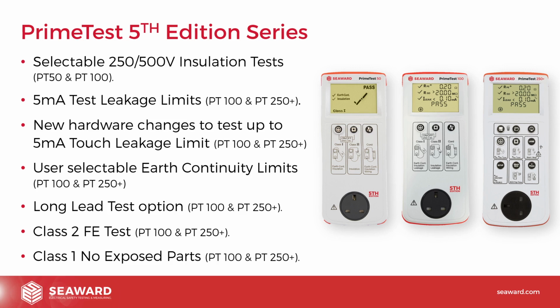So less skilled users, and we talked earlier in the webinar about the level 1 users, level 1 competency, will be able to carry out tests knowing that they're not going to damage any equipment and they're not going to have to change the settings or anything like that. So it defaults to 250 volts. And if you want to test at 500 volts, you hold the test button down longer and it changes over for that particular test to 500 volts. It'll carry out the 500 volt test and then give you the pass or fail. So on the Prime Test 50, that's just a simple user interface. It defaults to 250, but if you hold the button down longer when you do the test, it'll change over to 500.